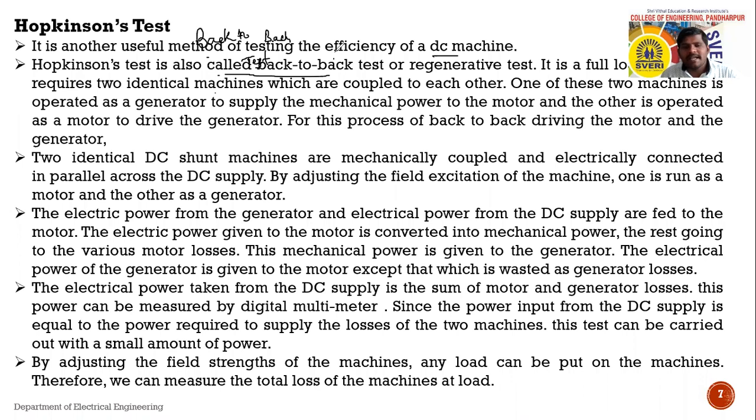This test is also called the back-to-back test, or we can call it the regenerative method of testing. In this method of testing, we require two identical machines, and both machines are running on full load condition.